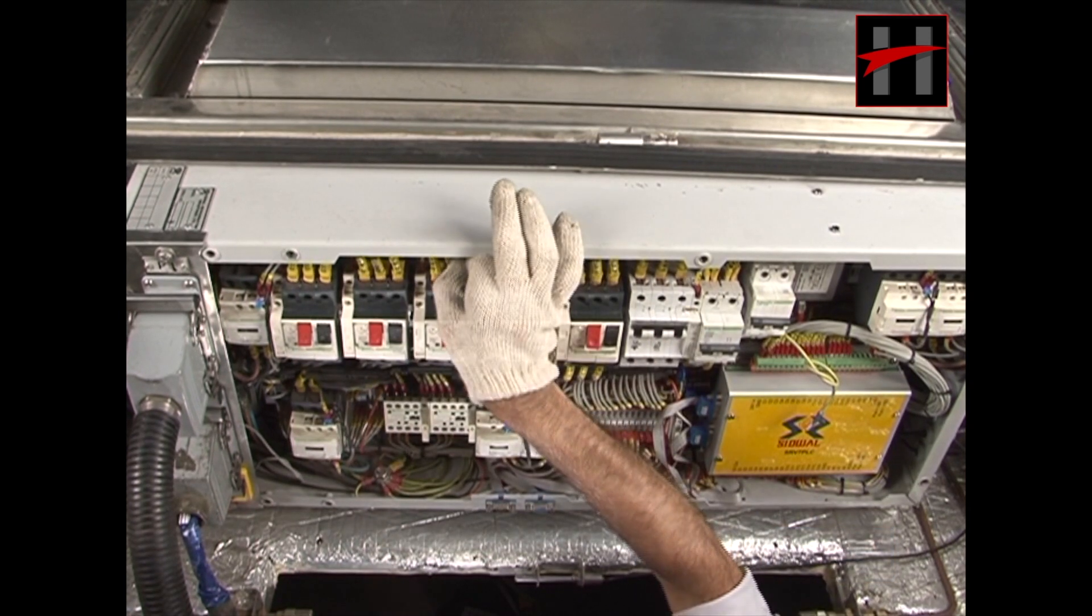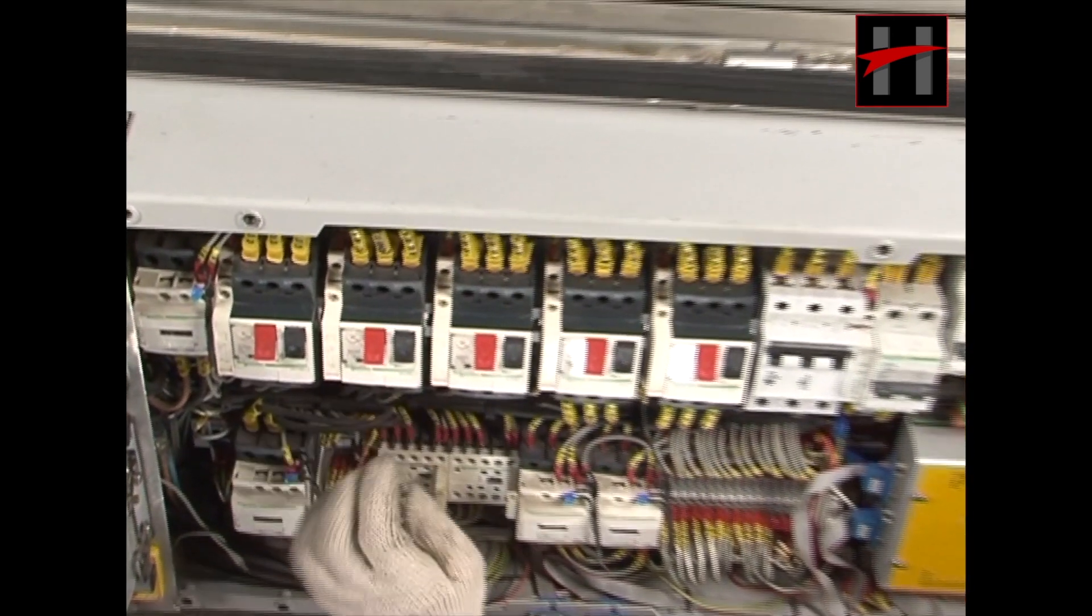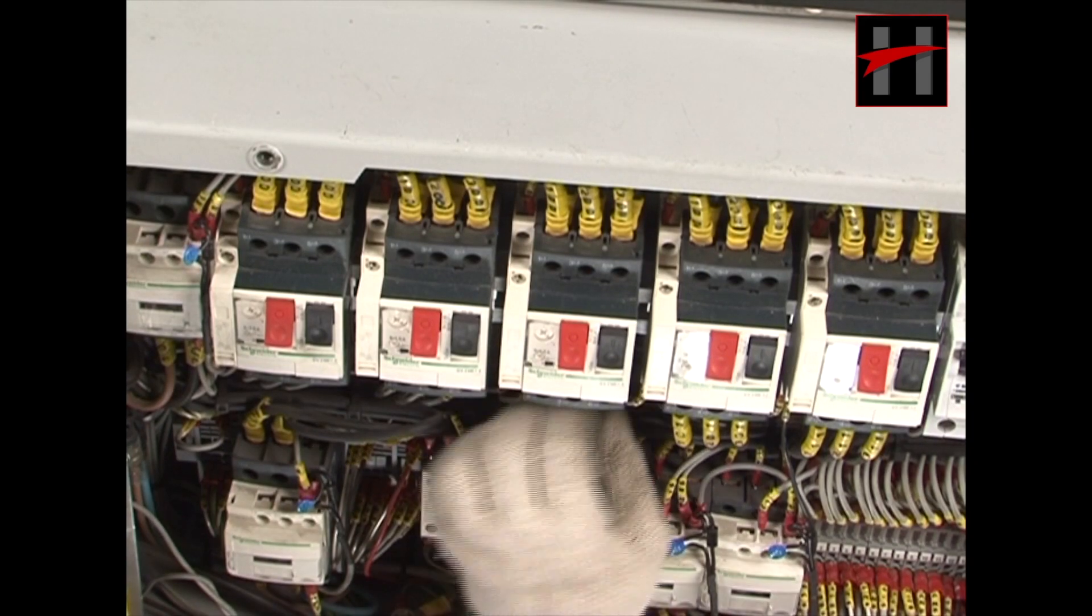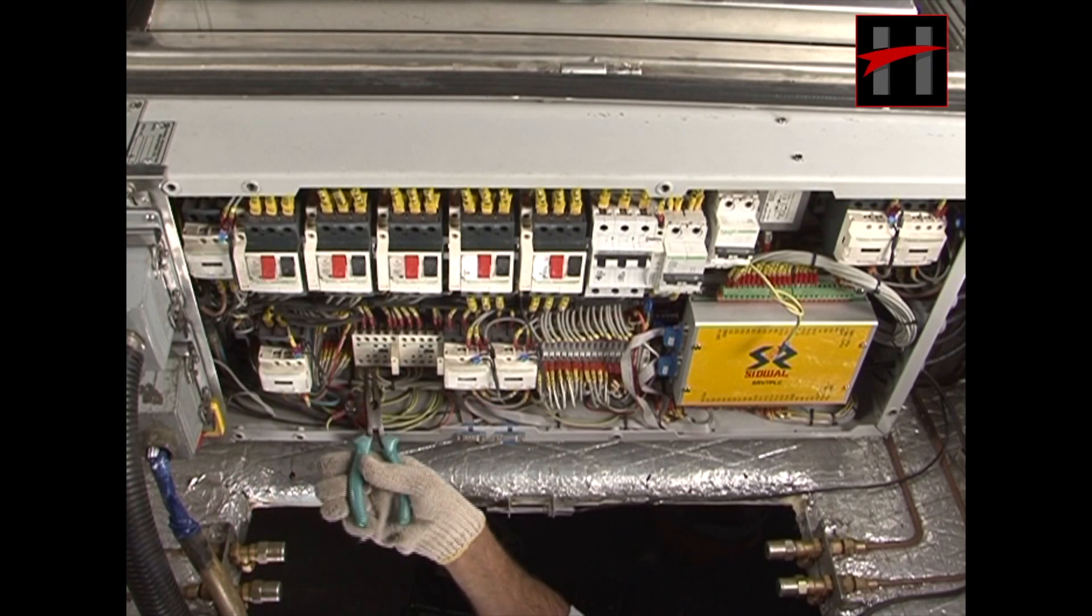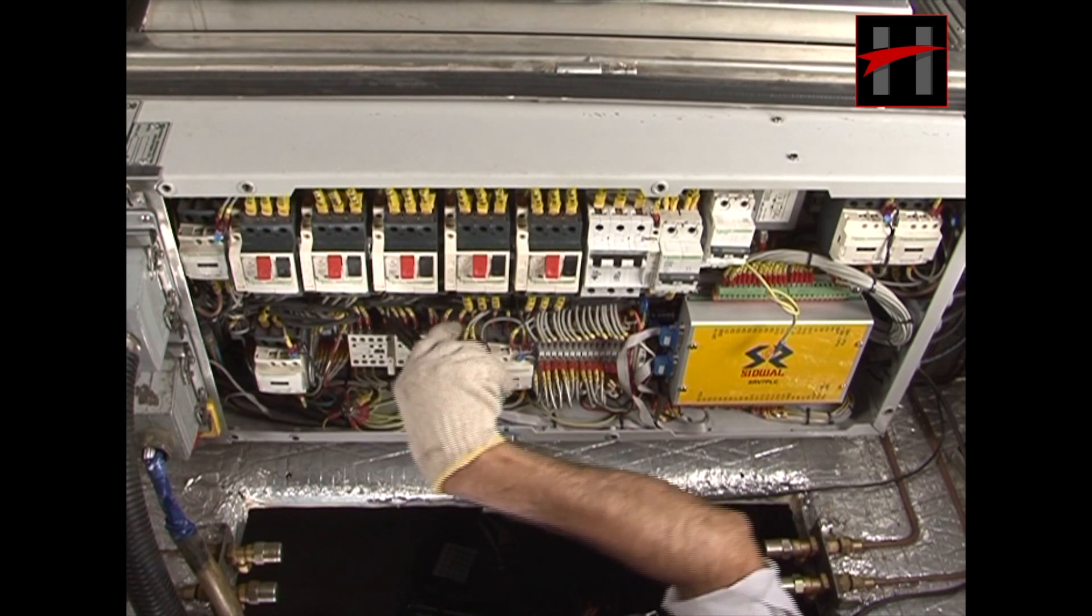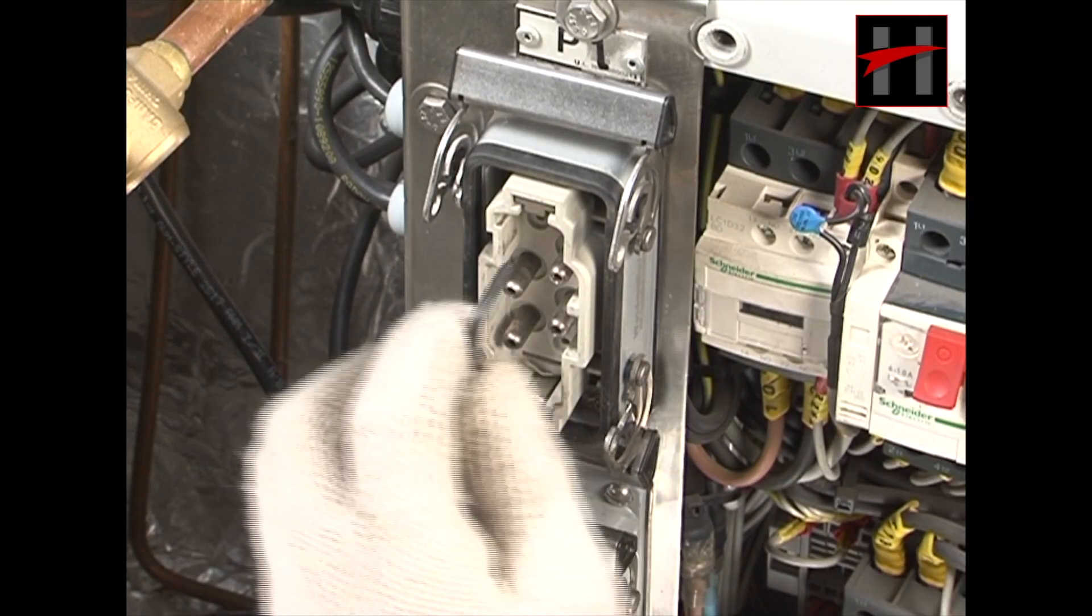If it is found tripped, check the wiring of the condenser fan circuit breaker, circuit breaker contactor, and the P1 connector.